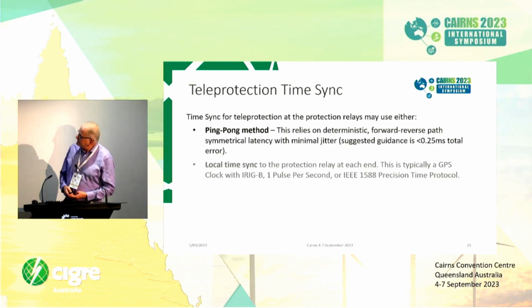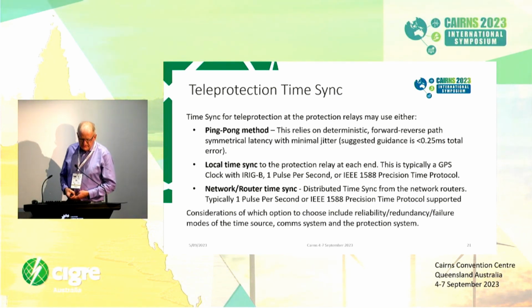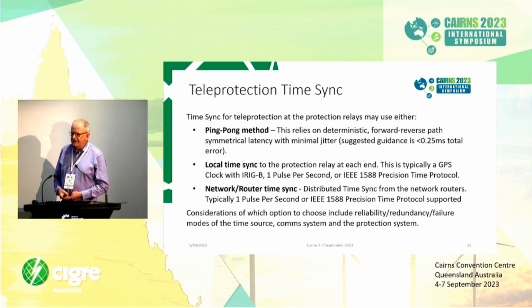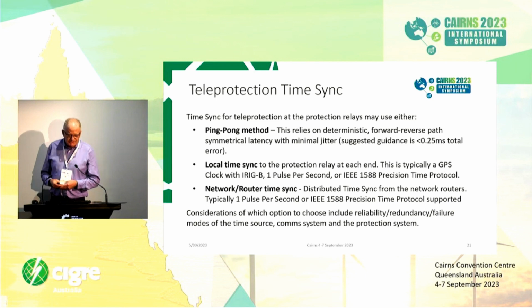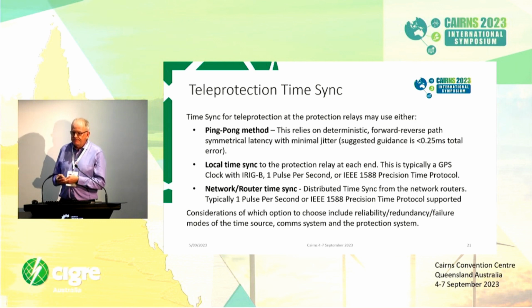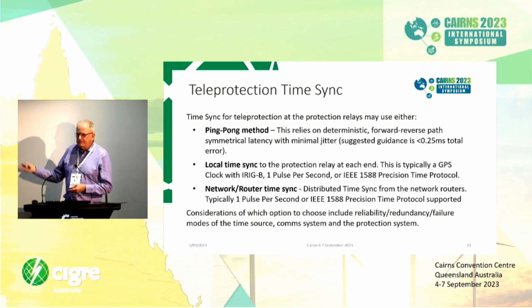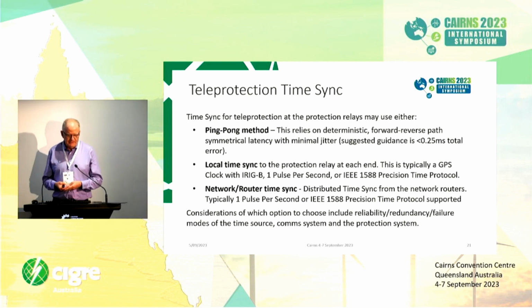Just a bit about time sync. As we said, the protection relays themselves can use a ping pong method where they send a signal through the communications network, and they look for that return message coming back to the relay. Then they calculate a round trip latency and determine the actual latency in one direction by simply halving the return trip time. That's one of the reasons why symmetrical latency is so important, because the protection relays use the round trip time, halved, as their means of calculating the single path unidirectional latency.